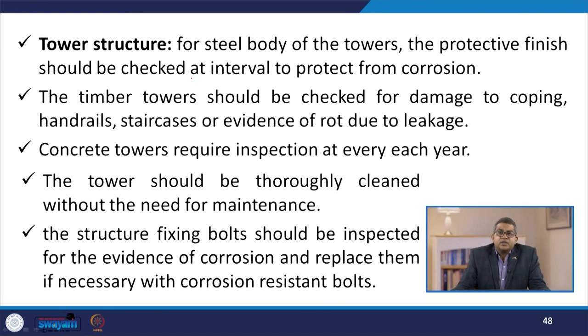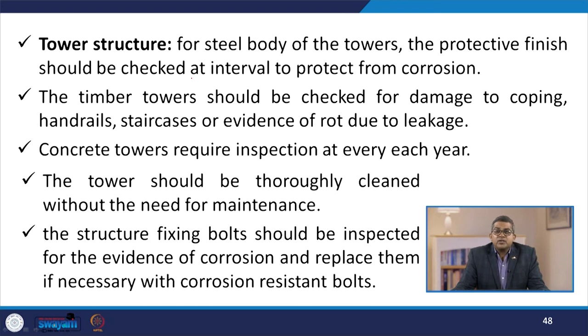Tower structure: for a steel body tower, the protective finish should be checked at regular intervals to protect from corrosion. Timber towers should be checked for damage to coping, handrails, staircase, or evidence of rot due to leakage. Concrete towers require inspection every year. The tower should be thoroughly cleaned as part of maintenance, and structure fixing bolts should be inspected for evidence of corrosion and replaced if necessary with corrosion-resistant bolts.